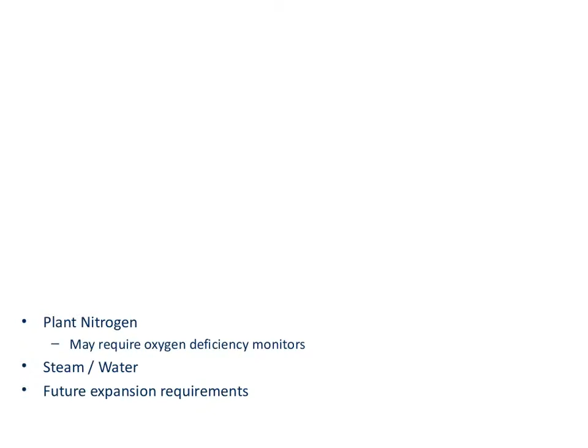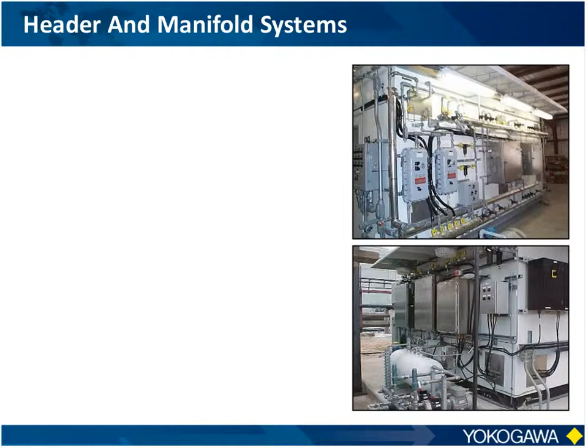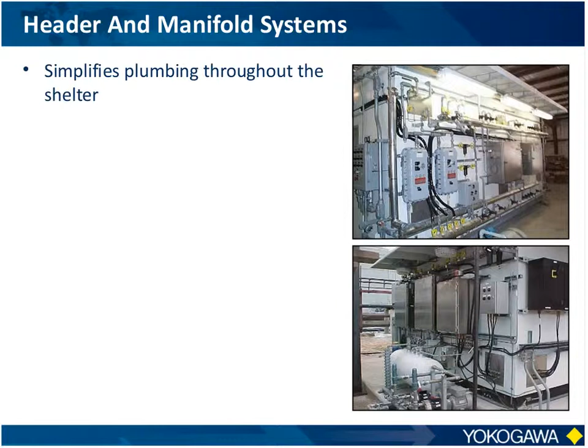As part of the design of the shelter, it's frequently a good idea to ask for what they call manifold and header systems, because a lot of the equipment uses common utilities like air and steam, and they have vent and waste gases that need to be collected. So being able to collect them all together in a tube that's common to them makes it a whole lot easier, because it really does simplify the plumbing throughout the entire shelter. And you can kind of see these on those pictures, those long tubes, especially on the upper one, that run along the horizontal there, where I'm bringing in all the gases and the vent gases.